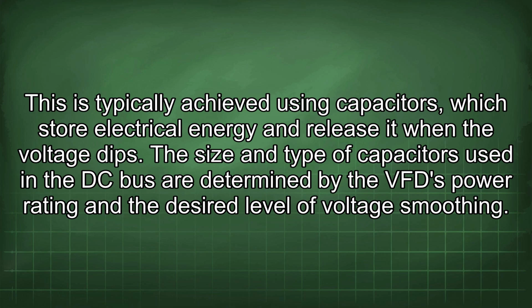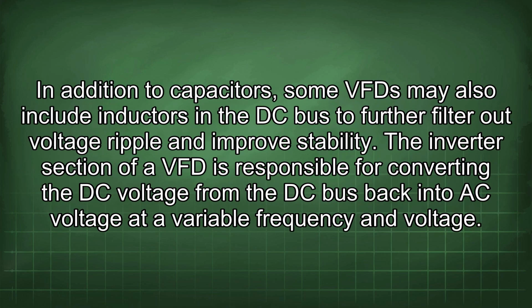The size and type of capacitors used in the DC bus are determined by the VFD power rating and the desired level of voltage smoothing. In addition to capacitors, some VFDs may also include inductors in the DC bus to further filter out voltage ripple and improve stability. The inverter section of a VFD is responsible for converting the DC voltage from the DC bus back into AC voltage at a variable frequency and voltage.